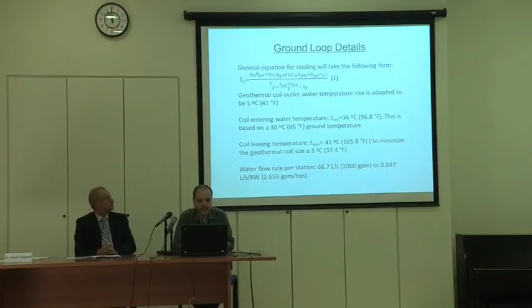The 36 degrees that enters through the air coil would return as 41 degrees, heated by the air that's at 46 degrees. We ended by estimating the flow, and that flow was around 66.7 liters per second for that station. We started identifying the different parameters to identify the lengths of the geo exchange, or lengths of the pipes. We started by identifying the diameter of the pipe in order to minimize the friction loss within that pipe. We selected it to be 1 inch.